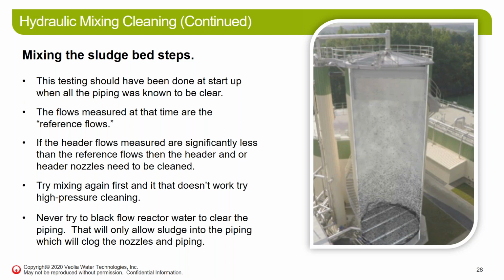But again, the key point here is never try to backflow the reactor water to clear the piping. That only allows sludge to come back into the piping and clog the nozzles worse.